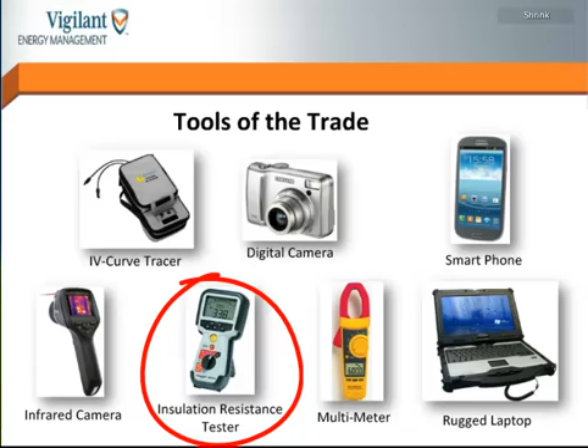The next picture is a handheld device called an insulation resistance tester, or a megger. It's designed to check for scrapes or breaks in the plastic insulation of conductors. If you're pulling wires through a conduit and scrape them without noticing, and the insulation is compromised, you have a chance for an arc fault or arcing. This device checks for that. It's very important during commissioning, but also useful during annual evaluations.